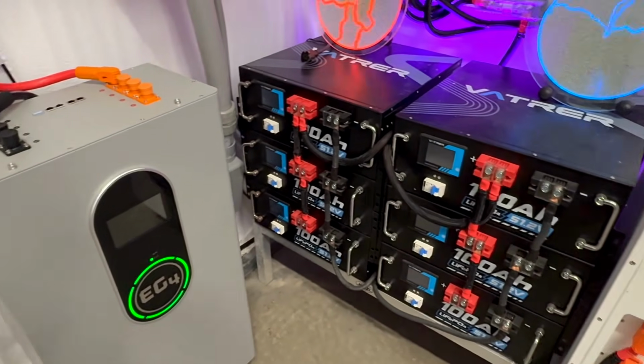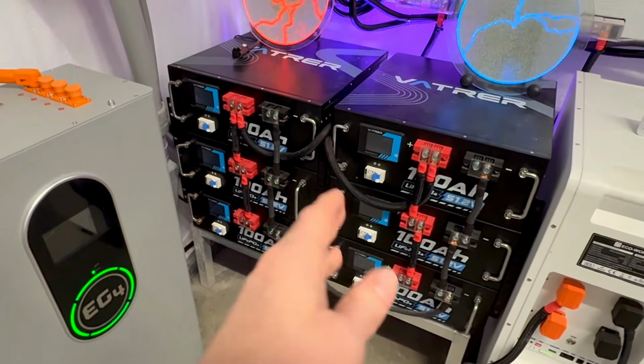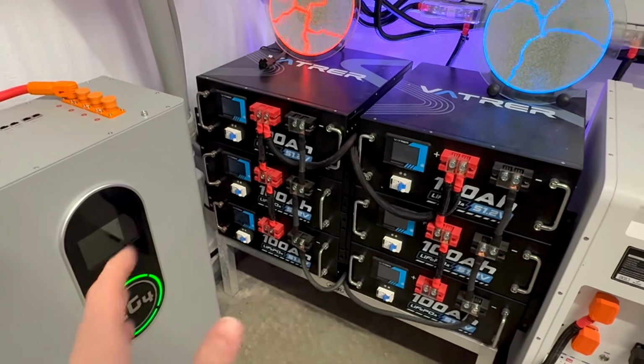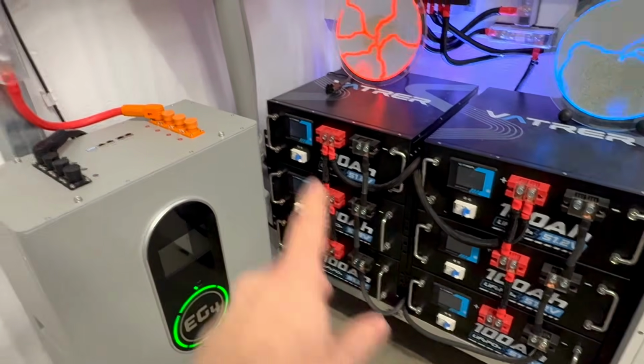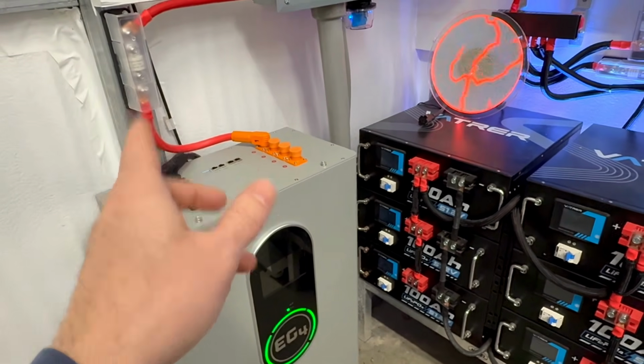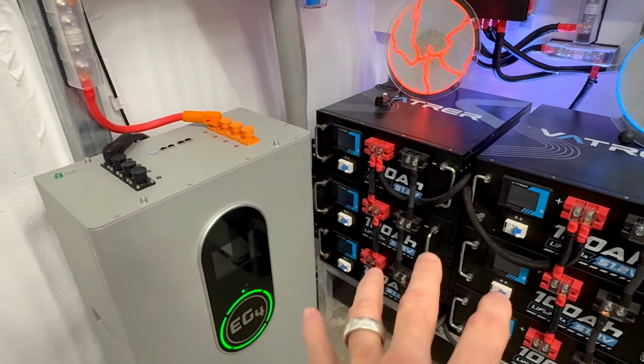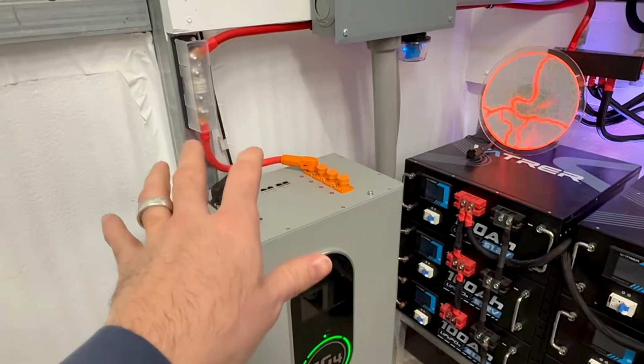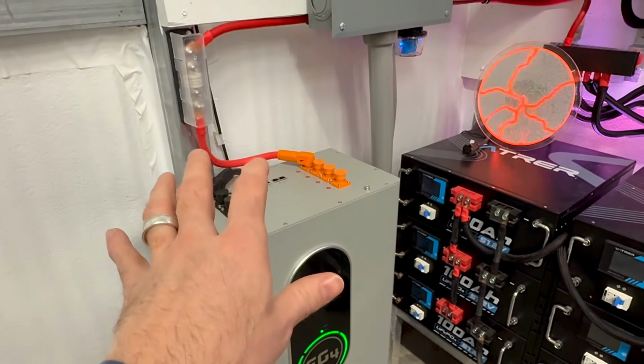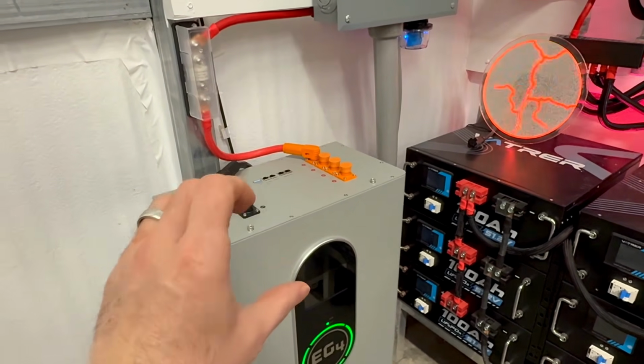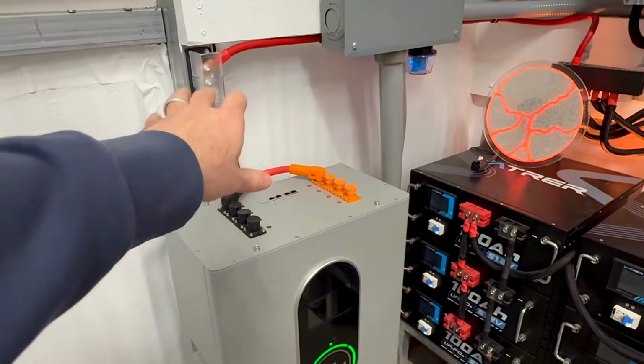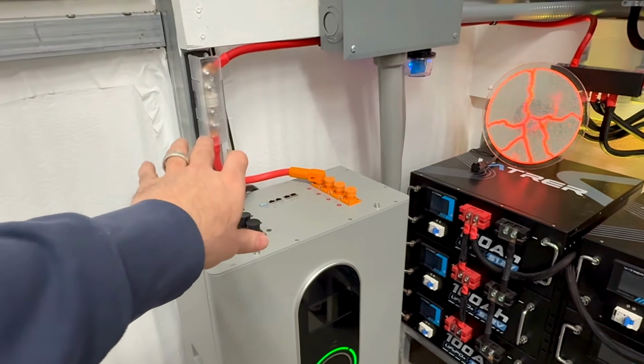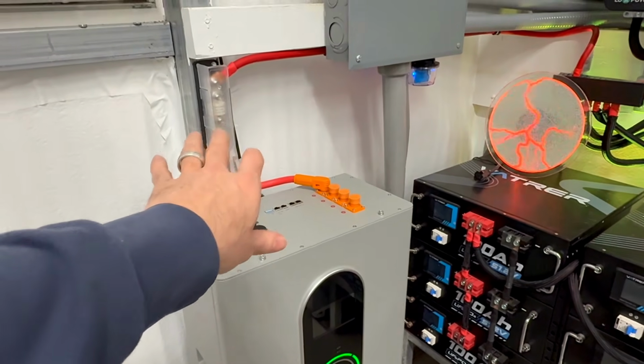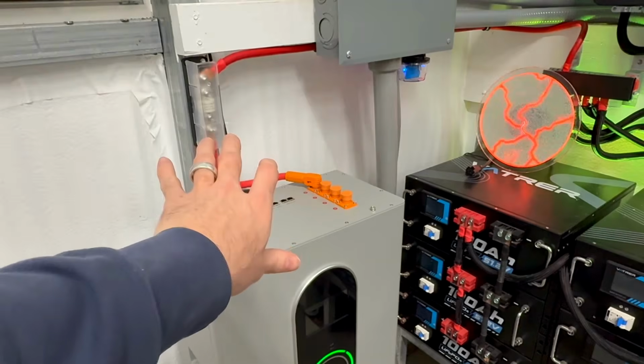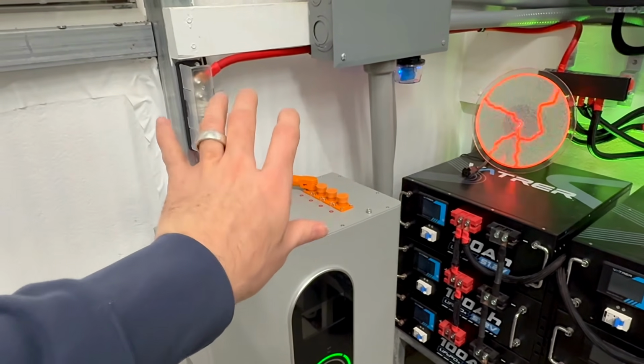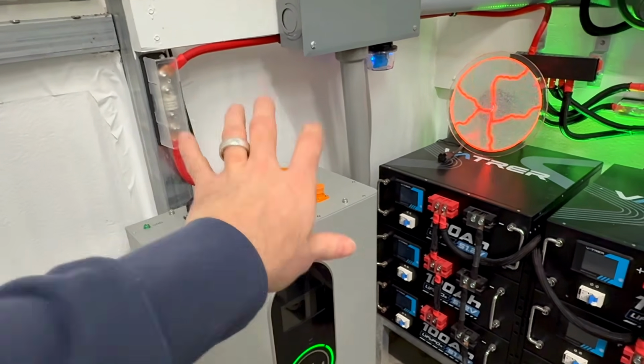What that does is give you a little redundancy, because if you have circuit breakers, those should trip fine. However, a fuse is always going to trip faster than a circuit breaker will. A fuse is also pretty much foolproof, especially if it's UL listed, and will interrupt that current flow. I believe these particular fuses have an interrupt current rating of 20,000, if I remember correctly.